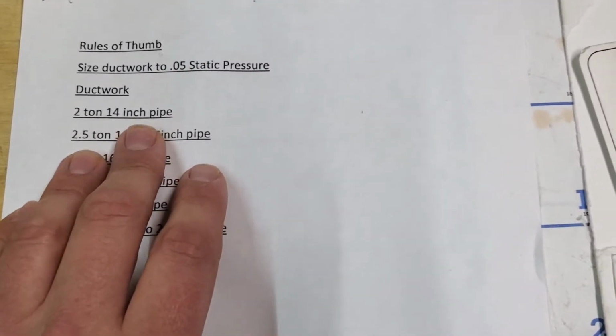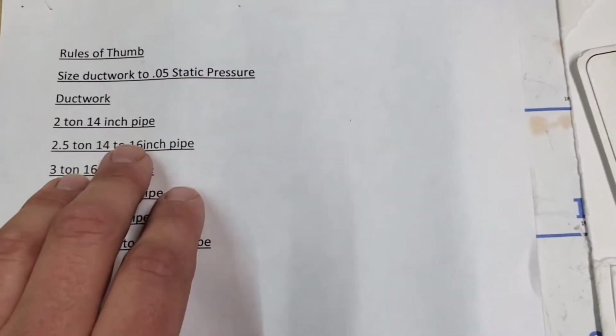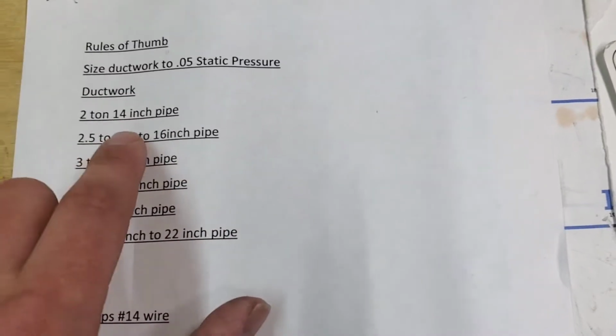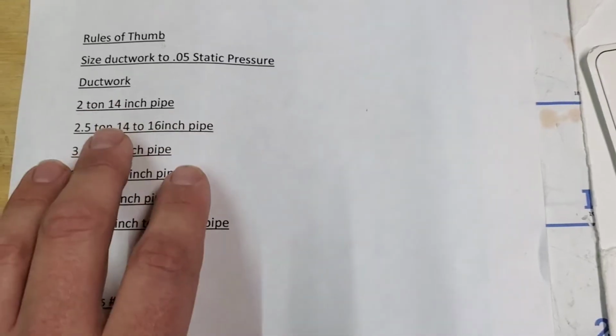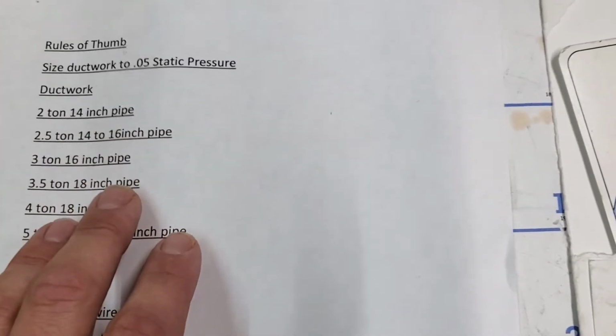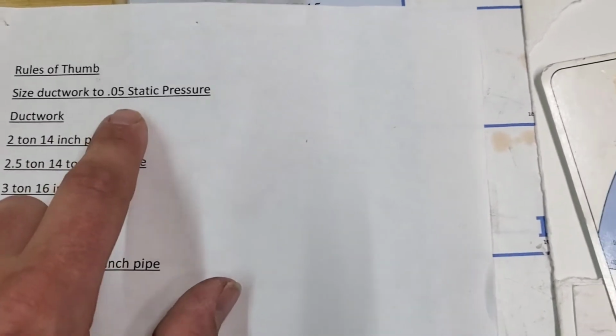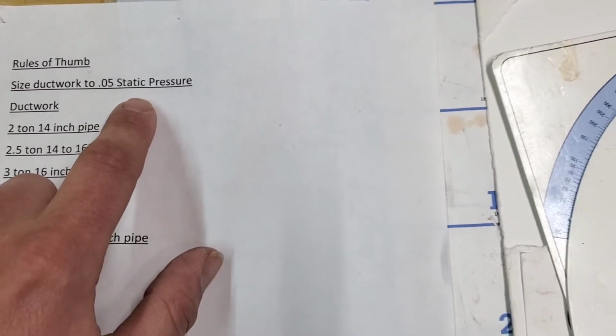This will give you a great rule of thumb to figure out, hey, is my ductwork even close to this? If it's lower than this number for 2 ton, it's not big enough. And let me tell you, 1 to 2 inches can make a big difference. Now, this is ductwork sizing to 0.05 static pressure, okay?